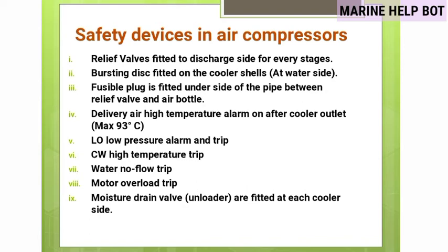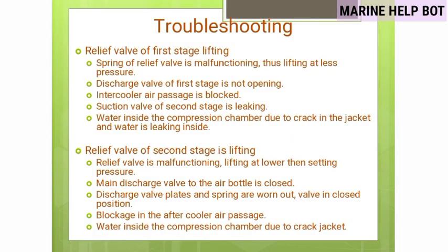Why is the first stage relief valve lifting? Causes include: spring of relief valve is malfunctioning and lifting at lower pressure; discharge valve of the first stage is not opening; intercooler air passage is blocked or choked; suction valve of second stage is leaking — high pressure air comes back and lifts the relief valve; or water inside the compression chamber due to a crack in the jacket — since water is incompressible, pressure rises and lifts the relief valve.